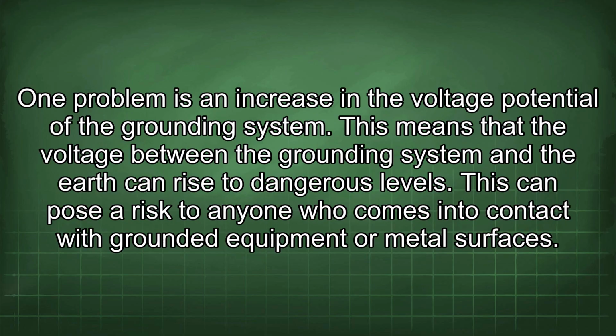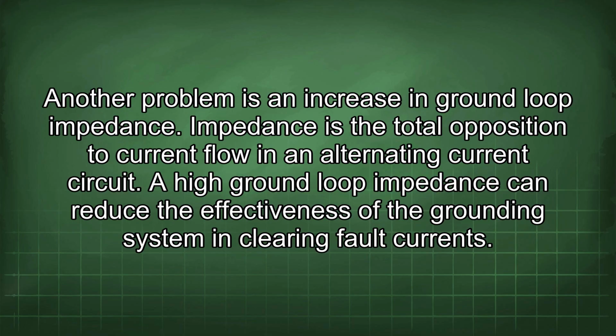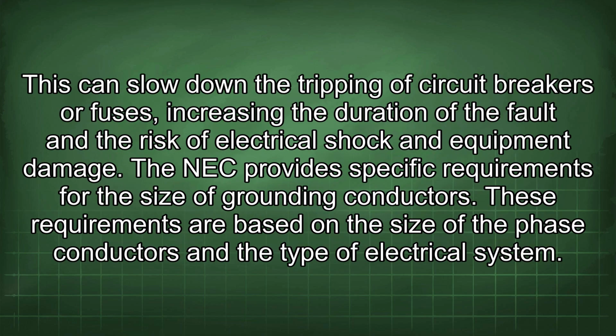One problem is an increase in the voltage potential of the grounding system. This means that the voltage between the grounding system and the earth can rise to dangerous levels. This can pose a risk to anyone who comes into contact with grounded equipment or metal surfaces. Another problem is an increase in ground loop impedance. Impedance is the total opposition to current flow in an alternating current circuit. A high ground loop impedance can reduce the effectiveness of the grounding system in clearing fault currents. This can slow down the tripping of circuit breakers or fuses, increasing the duration of the fault and the risk of electrical shock and equipment damage.